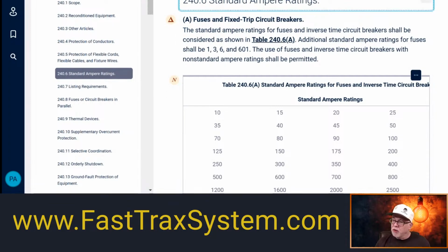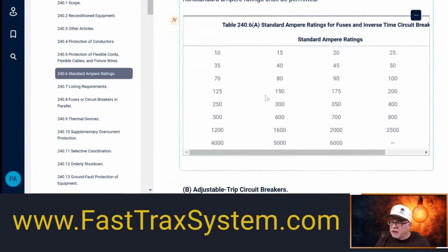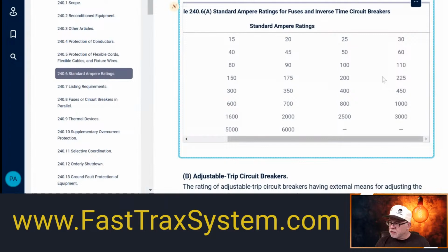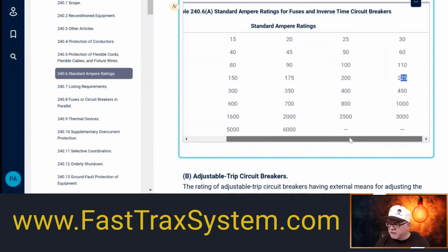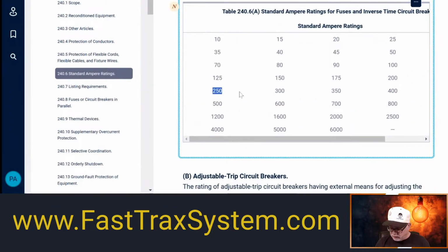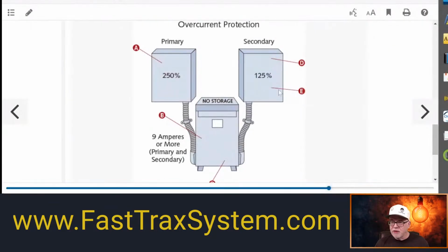All right, so we're over here, and let's see here. We have a 225. We have a 250, but we don't have a 260. So that next size rule says I could do what? It says I could go up. So I'm going to have 300 amps, okay? 300 amps. That gives me the allowance. So if I come back to our illustration, remember this primary side here was 225, and this secondary can be up to 300 amps.